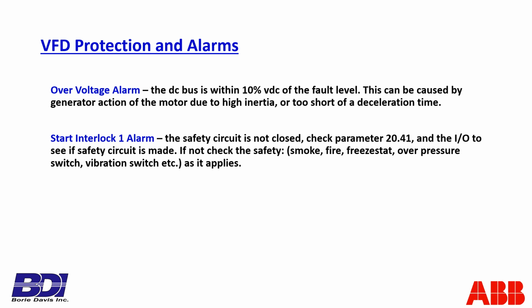There are some applications that don't even have a safety circuit, and that creates a little bit of an issue simply because the variable frequency drive is expecting a safety circuit to be wired into it. And so it comes ready to accept one, and if one isn't tied in, well, that's the same as saying the safety circuit's open. So if you don't have any separate safety circuit coming in, we're going to learn how to program that requirement away, because there isn't one in this application sometimes.